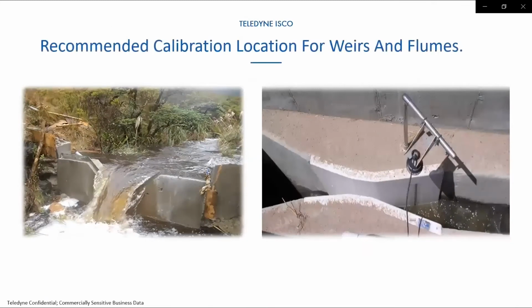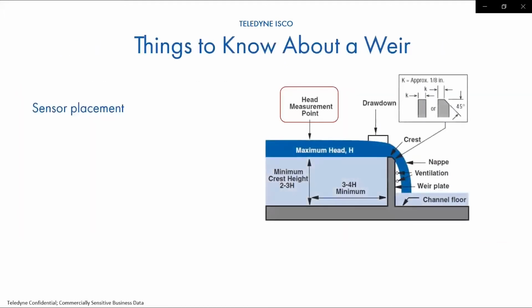So next I want to talk about the recommended calibration location for weirs and flumes. And so with the weirs and flumes, you're going to use the 3 sensors that I had previously mentioned with the ultrasonic, bubbler, or pressure transducer. Now let's first talk about a weir. So the sensor placement is going to be 3 to 4 times the maximum head height. So what you want to look at when you have your flume or weir is, determine what your expected maximum flow rate is. You can use the ISCO flow data handbook to then determine what the level is supposed to be at that maximum flow rate.